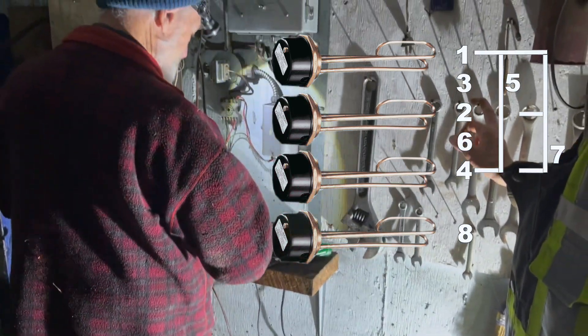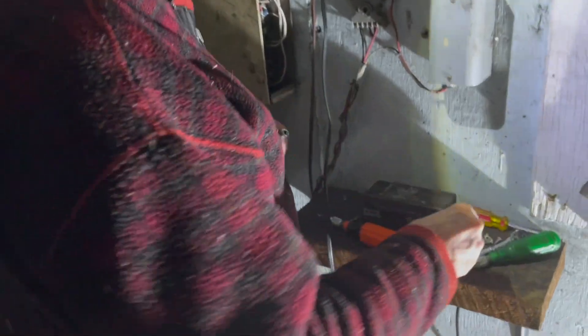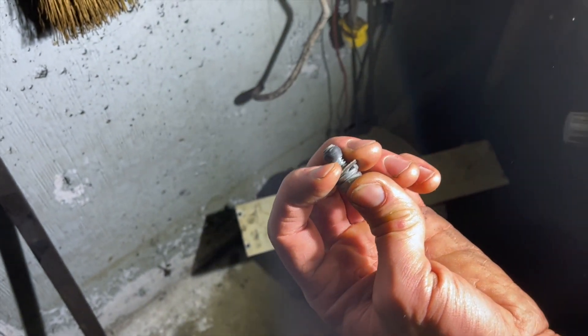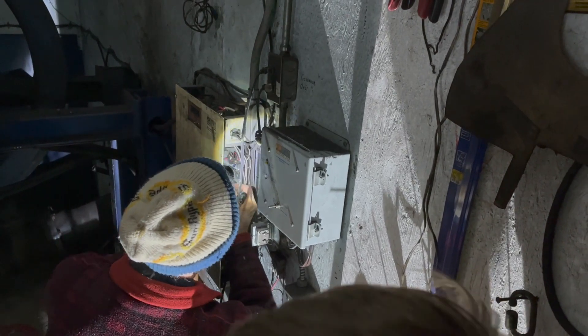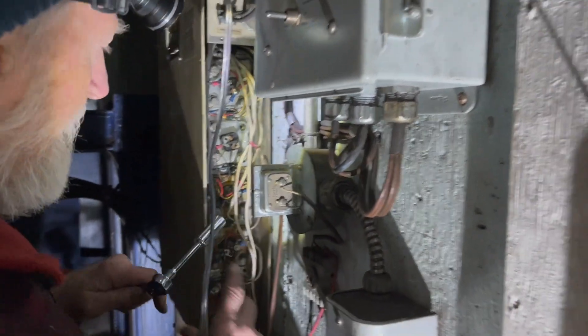It's a very high-powered version of a digital-to-analog converter. Notice there's an insulating washer here — that prevents corrosion of the element. It's got a sleeve and a gasket, so it's totally separated from everything. This is a box I have never looked inside — these things are so hard to work on. He's changed the design now; he got so mad at the one in his plant that he put all the electronics out on a separate board. So you have elements in one box and electronics in a separate box.